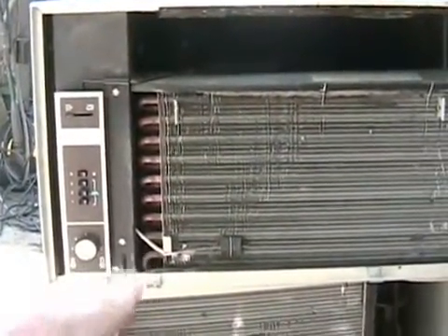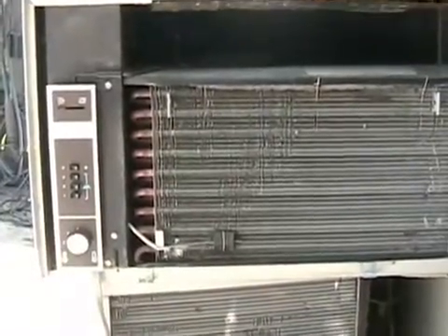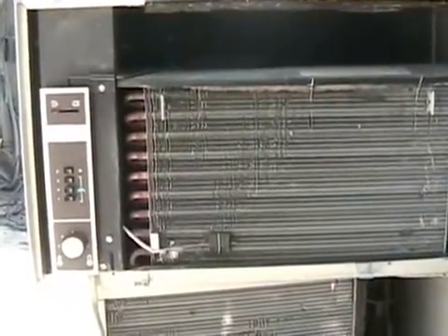When there isn't enough Freon in the system, it's low, all the tubes will not get cold like they're supposed to, only some of them will get cold, and they'll also form ice on the tubes, and that's bad, and that needs repair. In my next video, I'll describe how to repair air conditioners now that you guys have a bit of a redneck understanding how to understand heat and how, at least see how an air conditioner works.